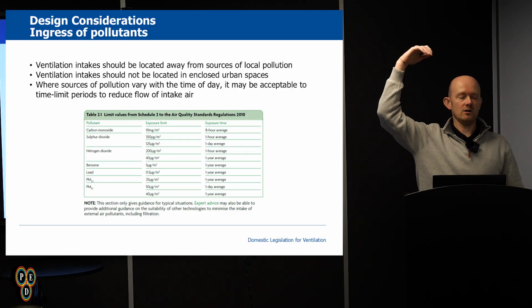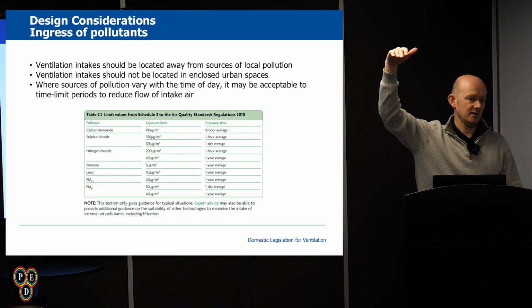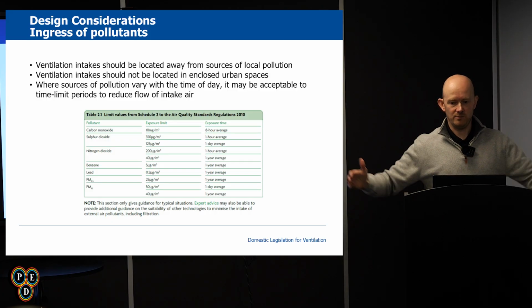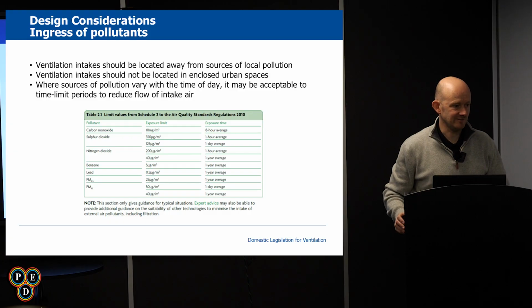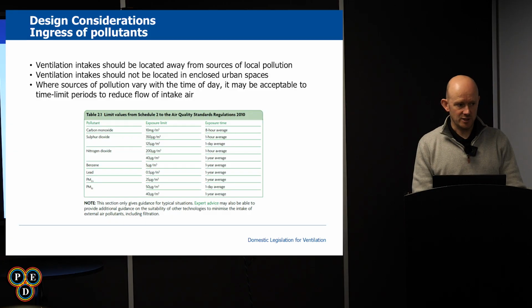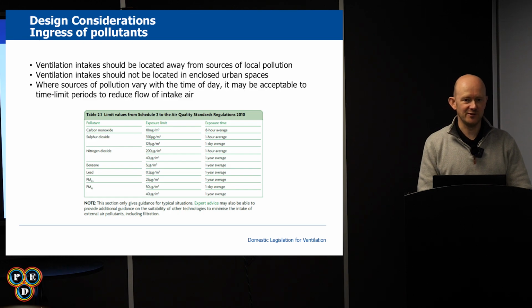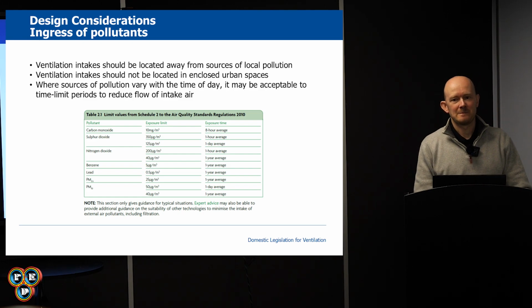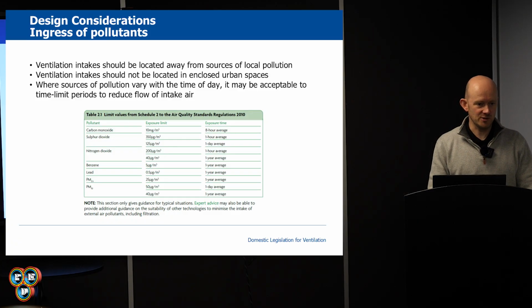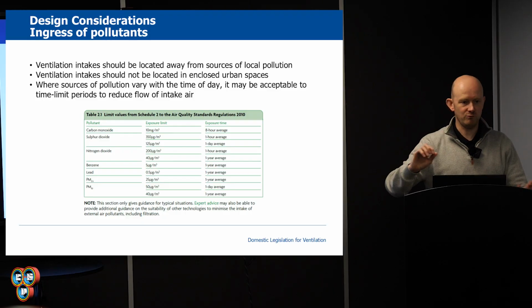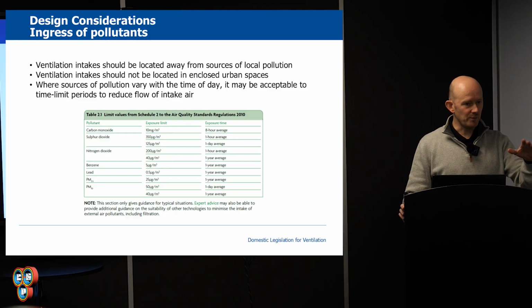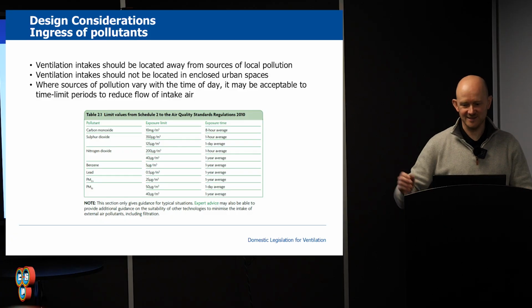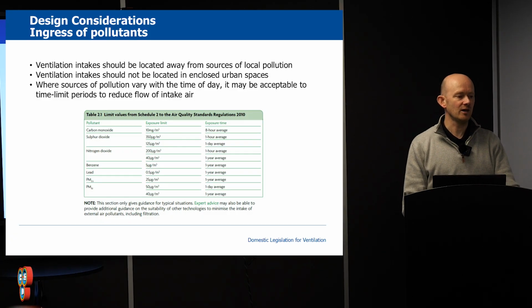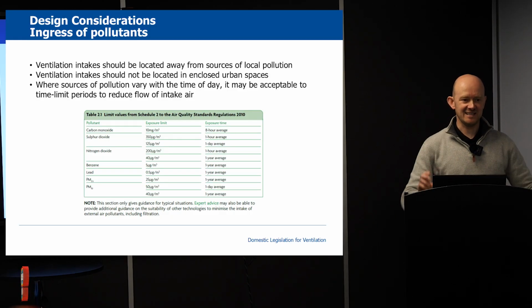And you've gone from having the architect wanting a 2.6 ceiling in this beautiful flat to like a 2.3 ceiling, because we've had to put a bloody great filter box in with an inspection hatch and everything. It's not great fun, and they have to be changed every 6 months, the filters. And the filter box costs £1,000. Not the filters, the filter box, but the filters are still a couple £100 every 6 months. So none of these consultants who just go put NOx filtration in, none of them work all this out. They don't care. No, but it will be your problem, which will then be my problem or someone else's. So just be mindful that if someone goes, oh, I've been told this house needs NOx filtration, just go, whoa, let's have a look at this first.